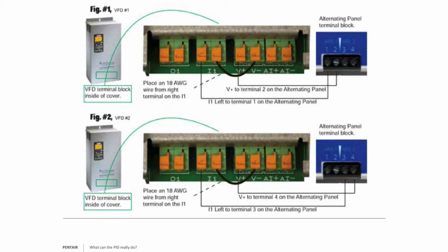So if we're using the alternator, we show you here, you run a jumper from V minus to input 1 or 2 minus, and then the 2 wires coming in from the alternator go to input 1 and the V plus. So that alternator, though it has its own power supply, that's for the counter and to control the relays to snap them open and close. Okay, it does not send voltage signal down into our actual PID drive. We're still borrowing the onboard power supply, as you see here.